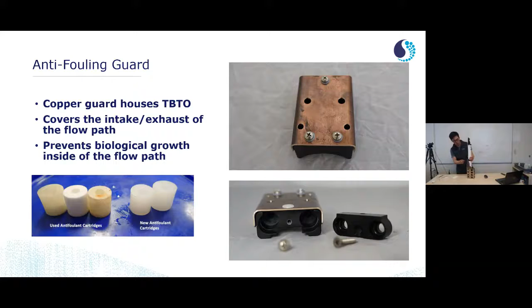Just keep in mind that if you start to see low conductivity or low dissolved oxygen, it could be biofouling in your instrument, and these cartridges need to be replaced. When you're handling these outside of the antifouling guard, always wear safety goggles and always wear gloves. They are toxic chemicals. So I'm actually going to take off the antifouling guard on this instrument before I put it into my tank of water, just so I don't get any trace amounts of TBTO into the water. So you can remove this pretty easily. So again, we're taking an Allen key, and you're going to put it into these top two holes here. So I'm just going to loosen each side. These screws are fully contained inside of the antifouling guard.